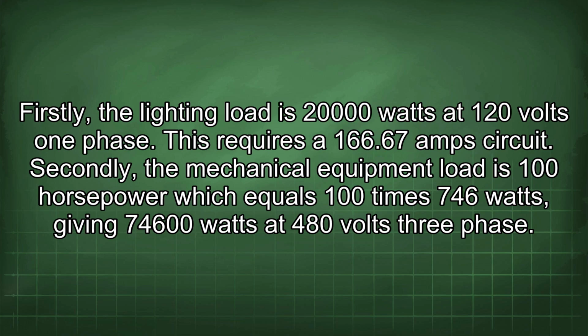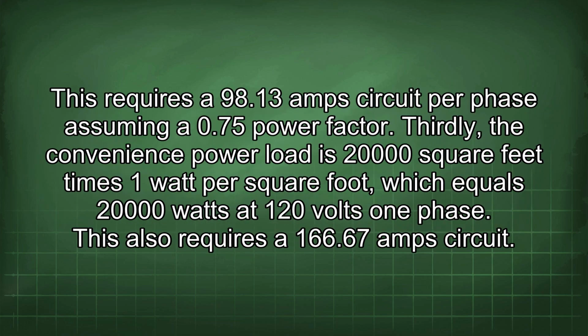166.67 amp circuit. Secondly, the mechanical equipment load is 100 horsepower, which equals 100 times 746 watts, giving 74,600 watts at 480 volts 3 phase. This requires a 98.13 amp circuit per phase, assuming a 0.75 power factor.